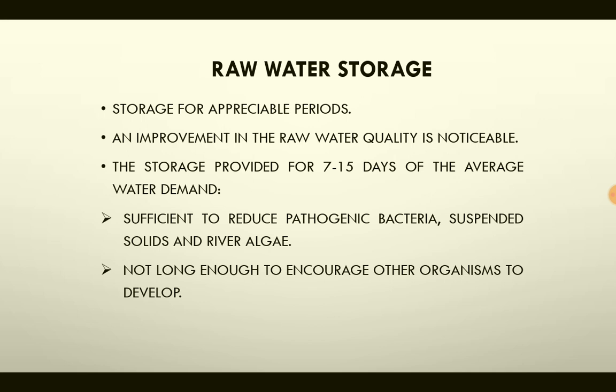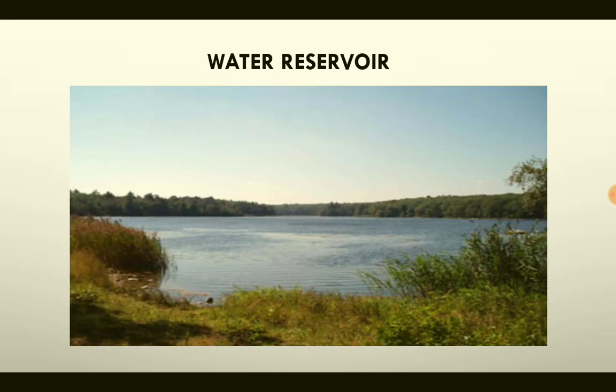The storage provided is for 7 to 15 days of the average water demand, which is sufficient to reduce the pathogenic bacteria, suspended solids and river algae, but it should not be long enough to encourage other organisms to develop, because it is observed that extended raw water storage facilitates the growth of microorganisms, algae, etc. This is a view of the water reservoir of a water treatment plant.